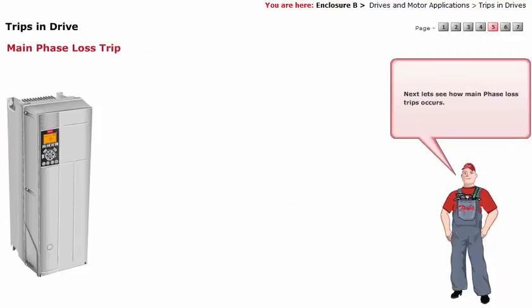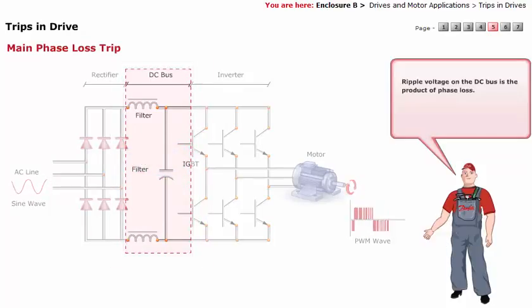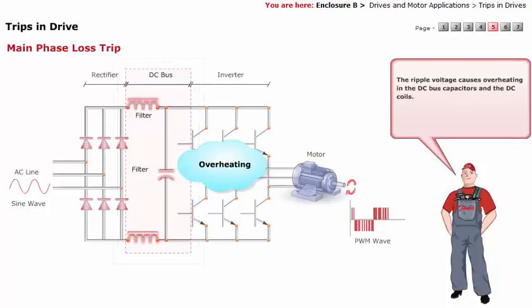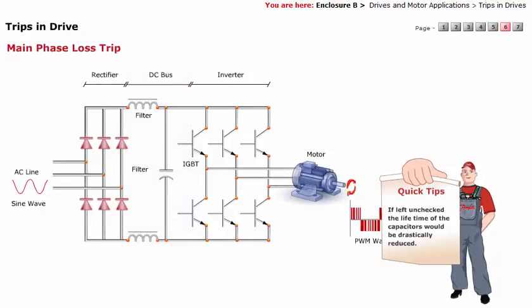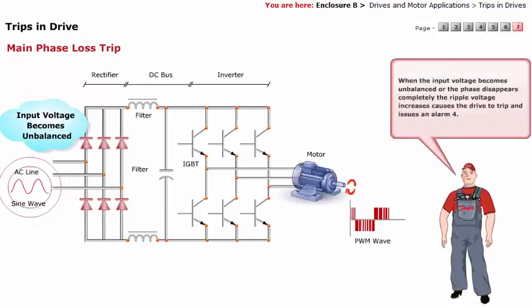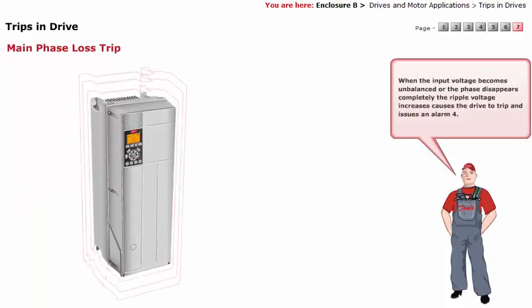Next, let's see how main phase loss trips occur. The drive monitors phase loss by monitoring the amount of ripple voltage on the DC bus. Ripple voltage on the DC bus is the product of phase loss. The ripple voltage causes overheating in the DC bus capacitors and DC coils. If left unchecked, the lifetime of the capacitors would be drastically reduced. Phase loss will only be detected if the load is larger than about 30 to 40 percent of full output load of the drive. When the input voltage becomes unbalanced or the phase disappears completely, the ripple voltage increases, causing the drive to trip and issue alarm 4.